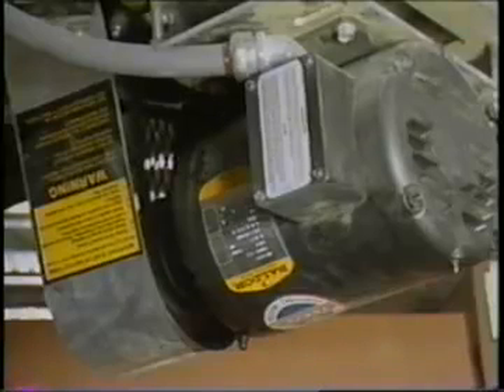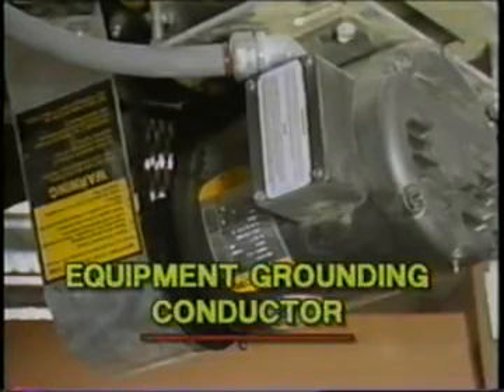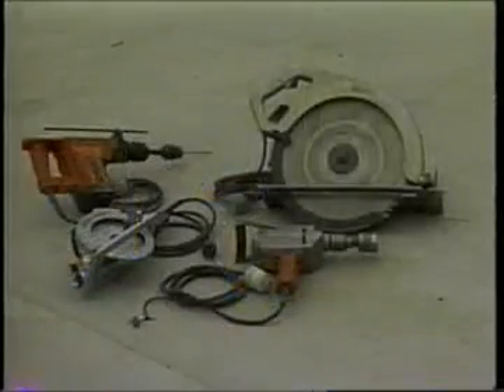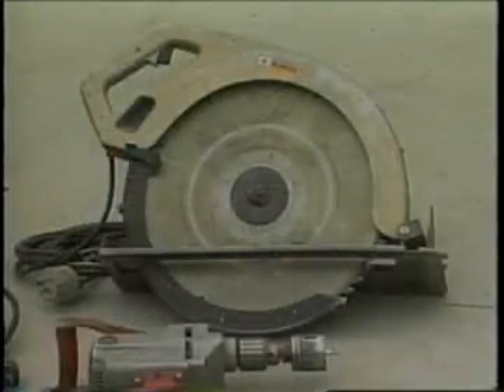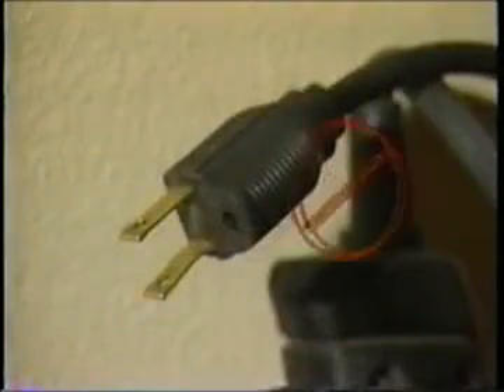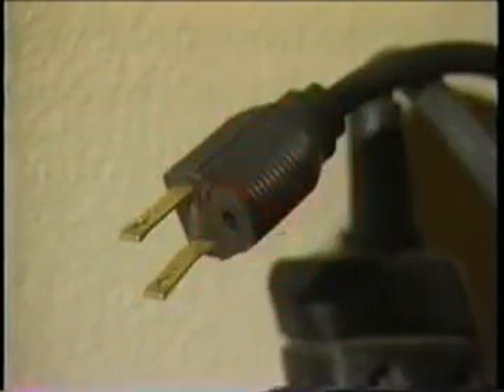Metal enclosures and containers are usually grounded by connecting them with a wire going to ground. This wire is called an equipment grounding conductor. Most portable electric tools and appliances are grounded by this means. There is one disadvantage to grounding. A break in the grounding system may occur without the user's knowledge.